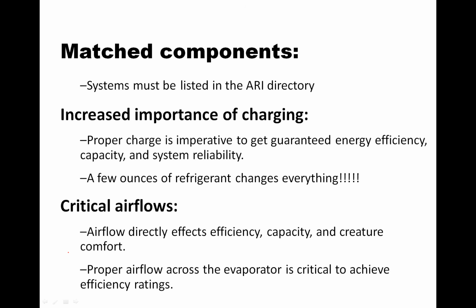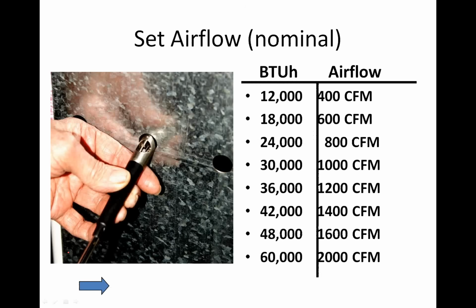Typically, manufacturers will list a matched evaporator size coil, 2-ton with 2-ton, and then they'll list a 2-ton condenser with a 2.5-ton coil. But you won't see a 2-ton with a 1.5-ton coil because that causes operational problems. So if you undersize the evaporator coil, you're going to have a whole slew of other issues you don't want to deal with.